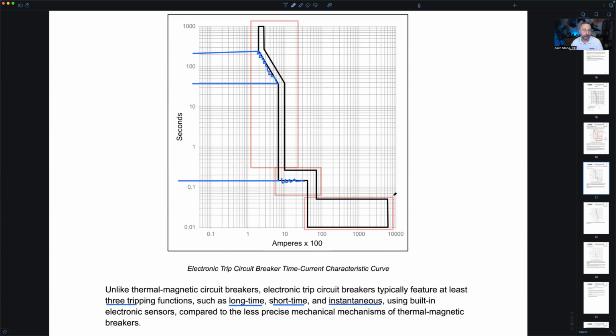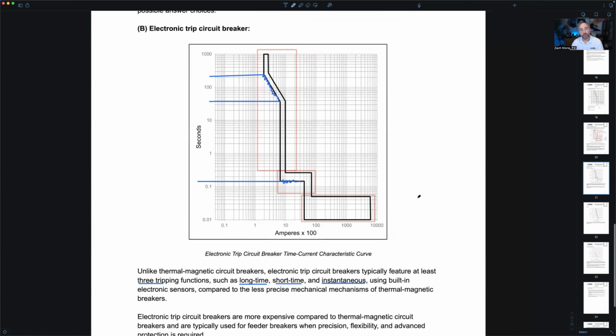Who can tell me why they are called electronic trip circuit breakers? Anyone work around these? And we'll compare them to thermal mag breakers. Really, they're operating with mechanical principles according to physics. The shape of it allows the magnetic field to try to pull apart the contacts on the instantaneous region. And then the metallic pieces inside, we use special pieces of metal that melt and typically we let a spring open the contacts for the thermal, right? These are mechanical properties. These are physical properties. How does an electronic trip circuit breaker work? Keyword is this word right here, electronic.